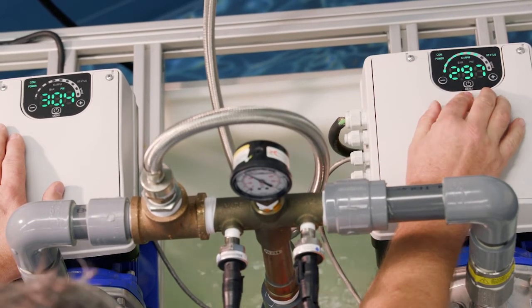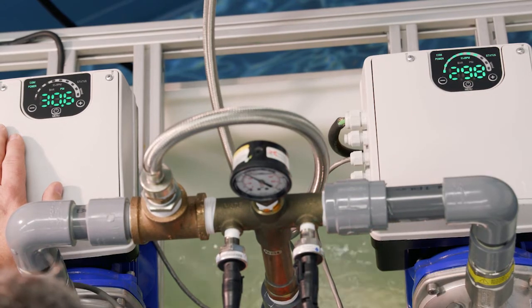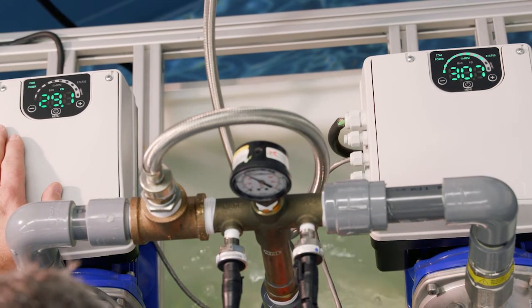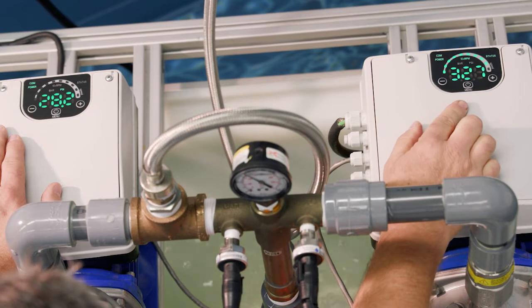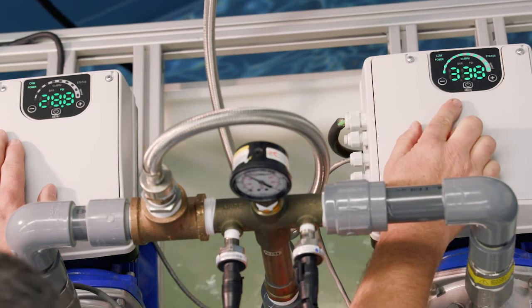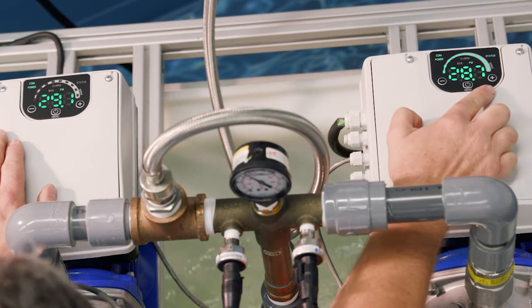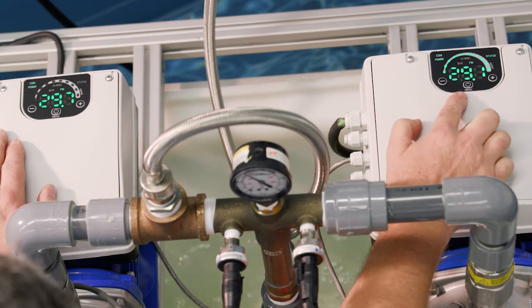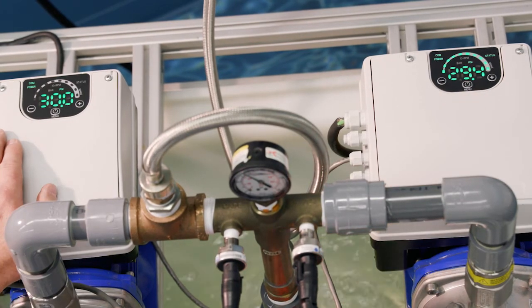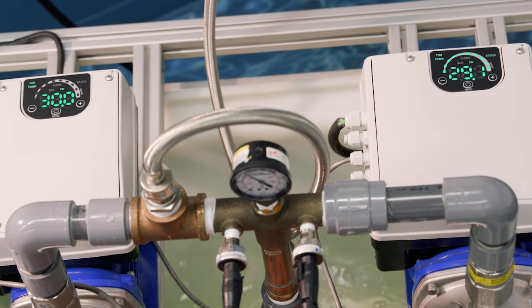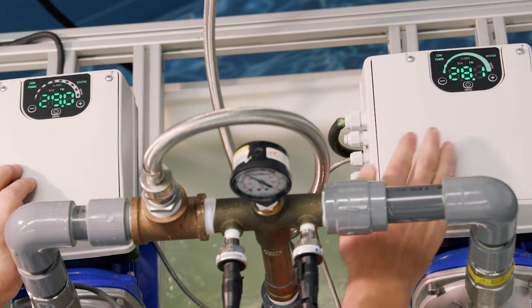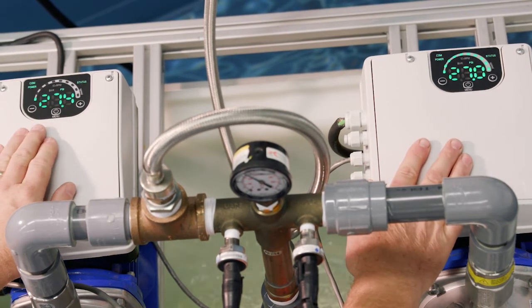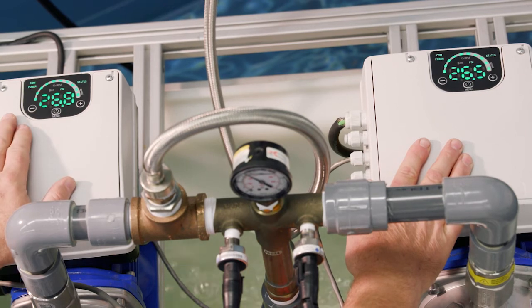So we'll just do that again. Take a look at speed. Open up the demand here. And the pump is speeding up to maintain that set pressure. And once it gets to full speed and cannot maintain that pressure, it's going to call for the second pump to come on. So we can see over here now, we've got both pumps running.